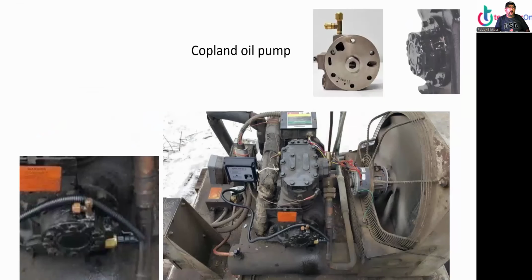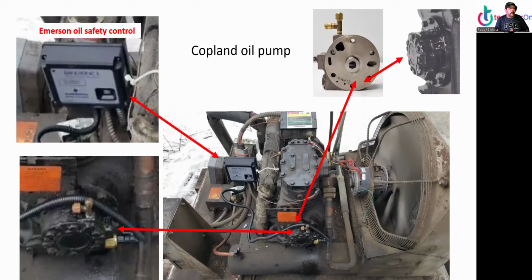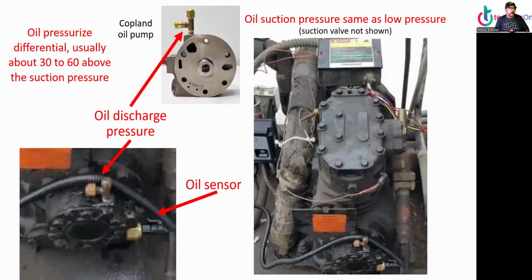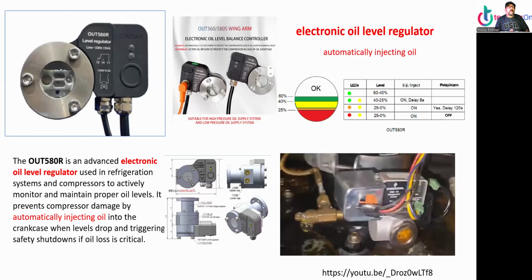All right, Copeland oil pump. There's the oil pump. You can tell it's an old compressor, but a new pump. And Emerson oil safety control. Oil pressure differential is usually 30 to 60 above suction pressure. Oil suction pressure is the same as low pressure. So we check the oil pressure to see if something is wrong. We don't check it unless there is an issue with the oil control. And we have the electronic oil level regulator.